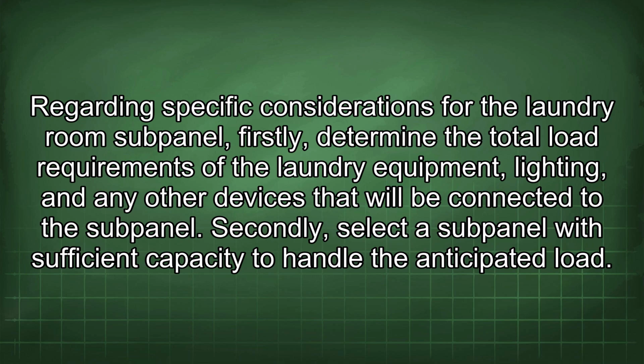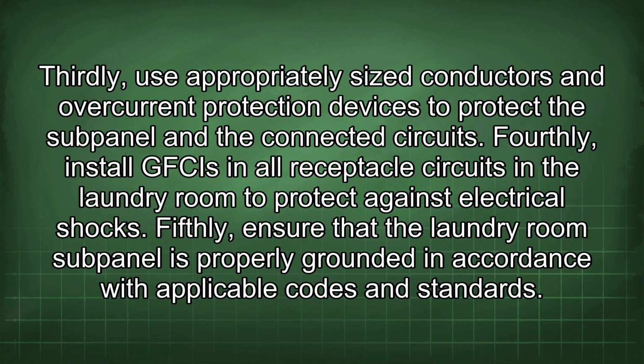Regarding specific considerations for the laundry room subpanel, firstly, determine the total load requirements of the laundry equipment, lighting, and any other devices that will be connected to the subpanel. Secondly, select a subpanel with sufficient capacity to handle the anticipated load. Thirdly, use appropriately sized conductors and overcurrent protection devices to protect the subpanel and the connected circuits. Fourthly, install GFCIs in all receptacle circuits in the laundry room to protect against electrical shocks. Fifthly, ensure that the laundry room subpanel is properly grounded in accordance with applicable codes and standards.